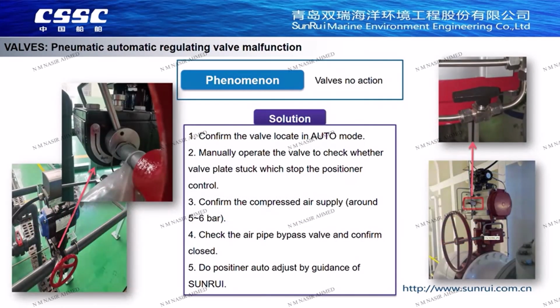Next one is a pneumatic valve that does not operate. First, check whether the valve engagement mechanism has been set to automatic mode. Open and close the valve under manual mode to confirm whether the valve body is stuck. Because our automatic valves are pneumatically driven, check whether the air supply is sufficient. Around 6 bar is the normal driving pressure. If the filter outlet valve malfunctioned, check whether the cylinder air bypass valve is closed. If there are no problems with the above, the valve shall be calibrated under the guidance of Sunrui.